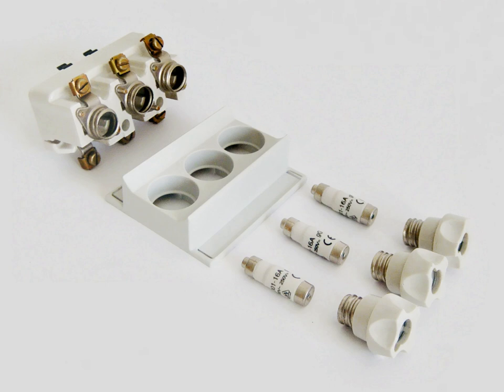Topic: D-type fuses. D-type diazed fuse cartridges have a bottle-shaped ceramic body with metal end caps and are fitted in screw-in fuse holders. They are available in 5 different body sizes, with ratings from 2A up to 200A. See table. The designation of a size consists of the letter D and a Roman numeral. Higher voltage types rated up to 750 volts have increased clearance distances and are longer than lower voltage rated fuses.